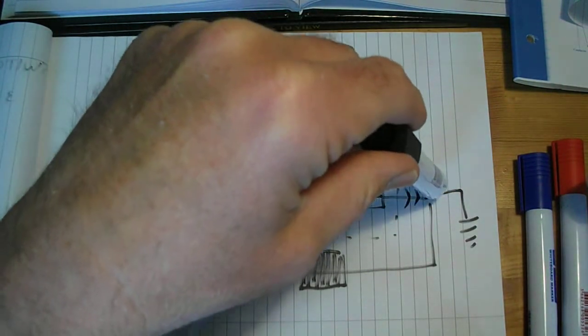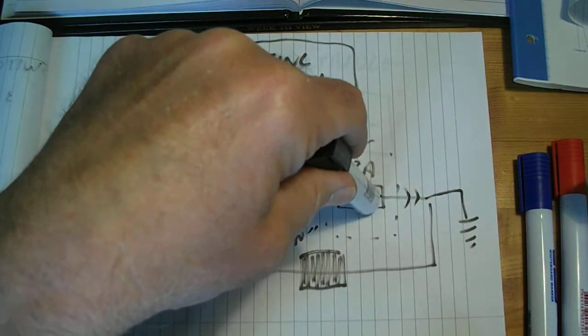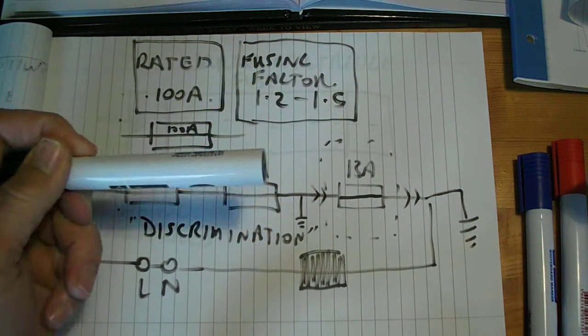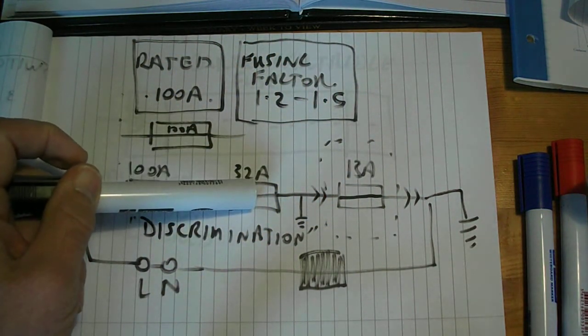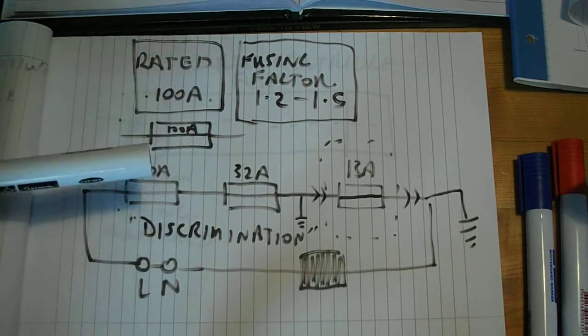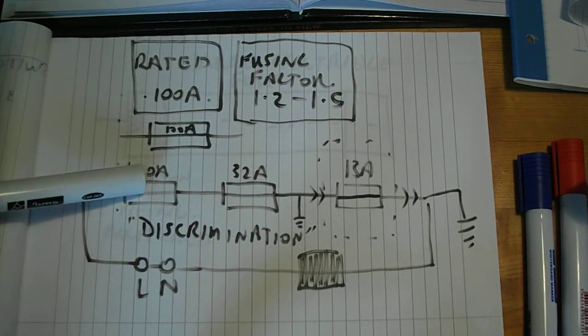So if, for example, in a washing machine a live wire came off and touched the metalwork of the machine, you'd get a lot of current flowing to earth, and we want this 13 amp fuse to blow before the 32 amp fuse or breaker in the circuit board, and definitely before the 100 amp fuse here.